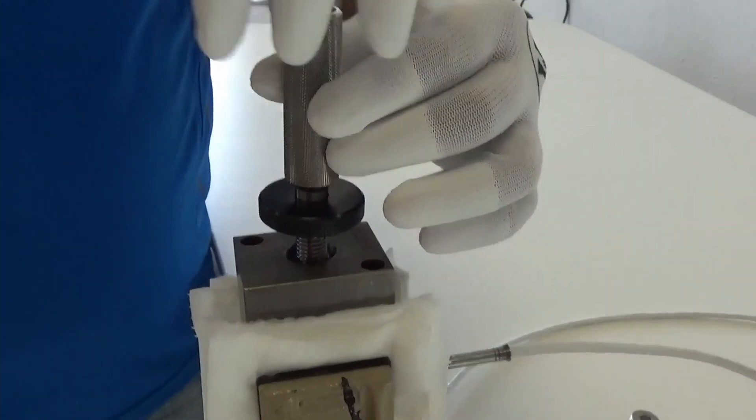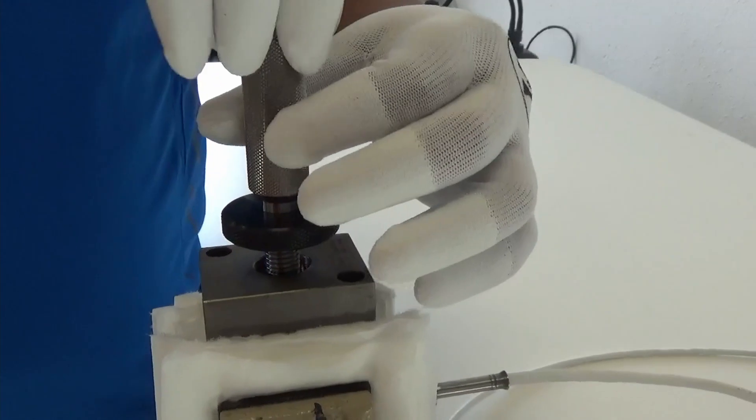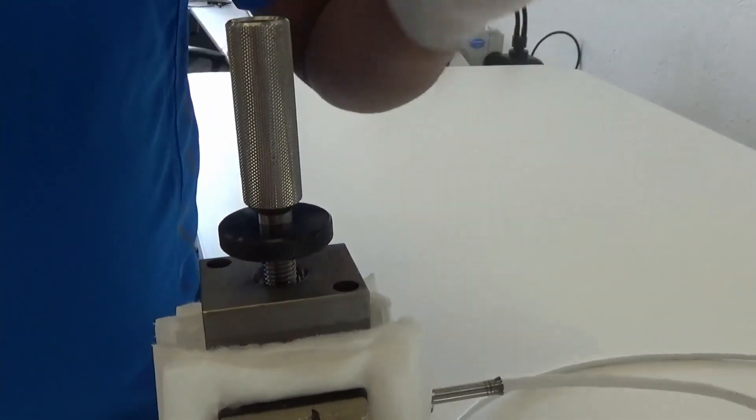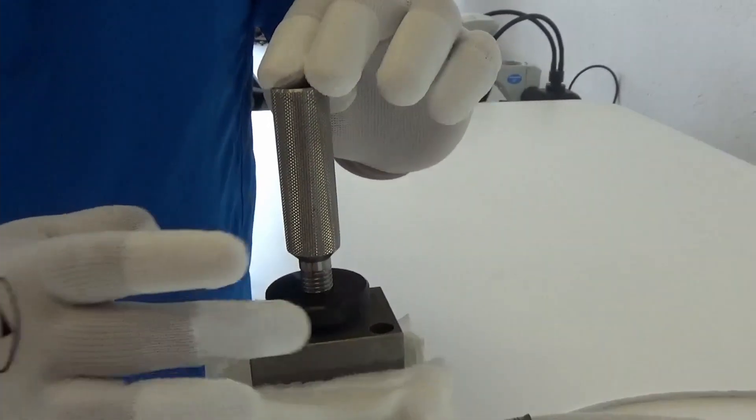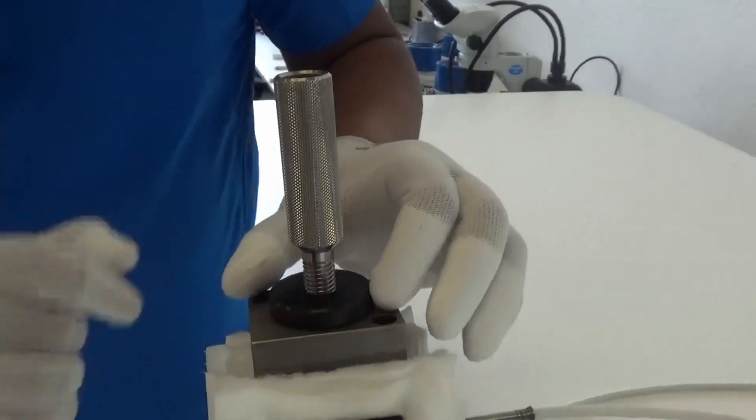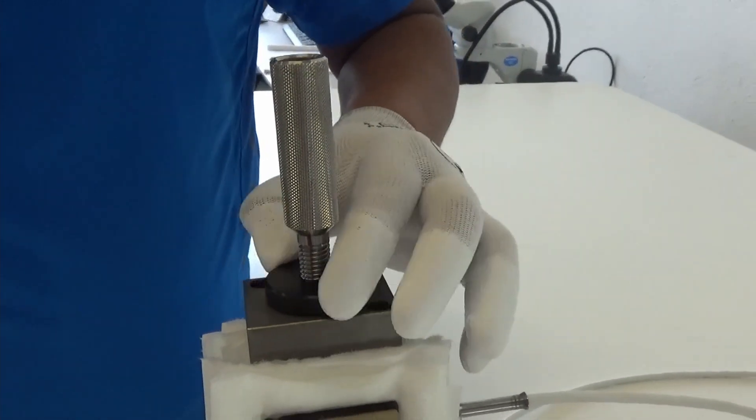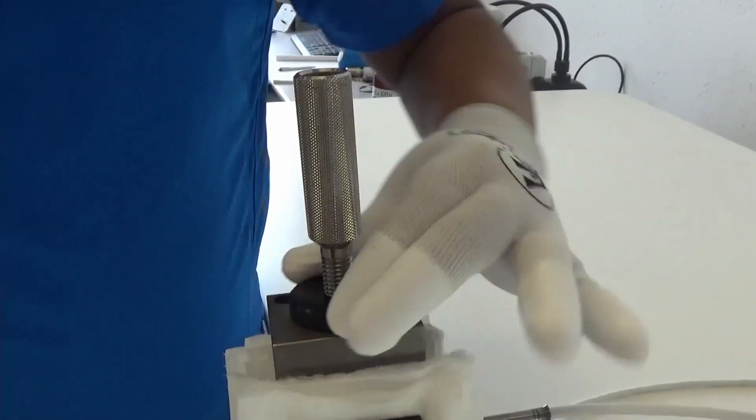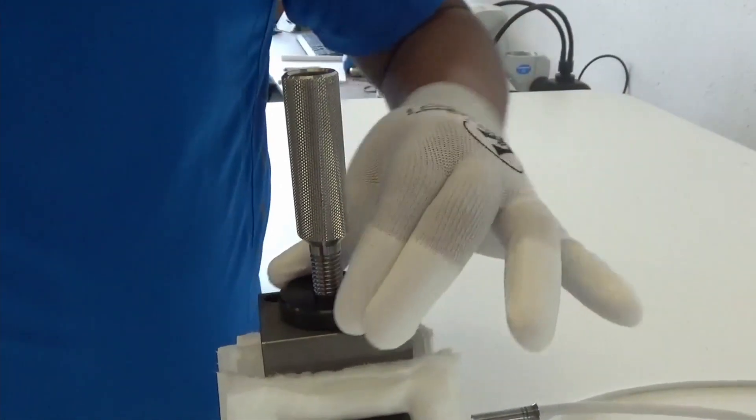Take the tool, thread it in nicely, gently, completely through. Now start moving the black ring down till it touches the surface. Then move it again gently and it's starting to extract the sensor from the body of the module, the DVM module. You'll feel that there is not much pressure, that's when you can take it out.